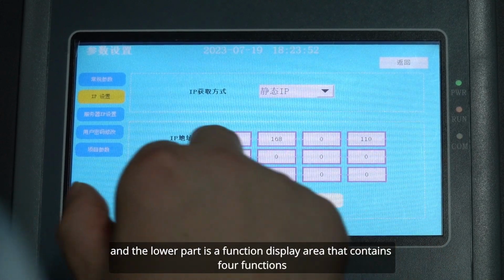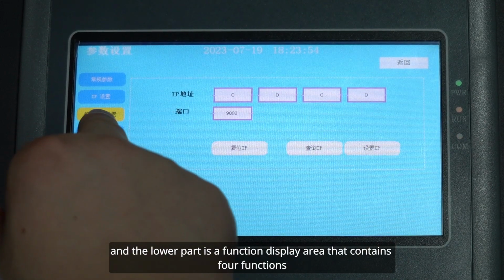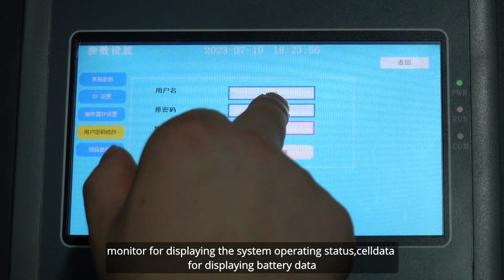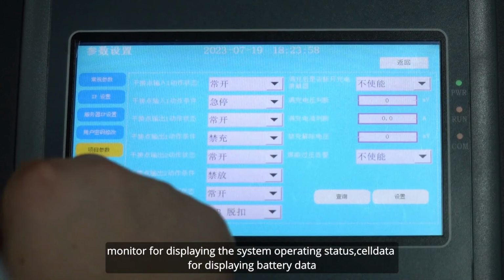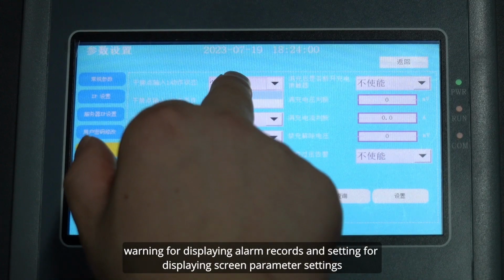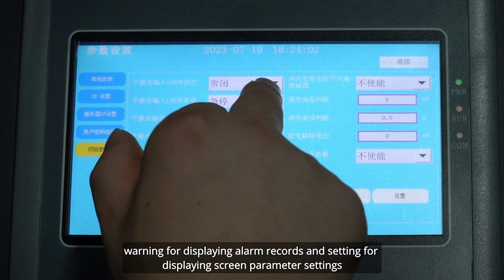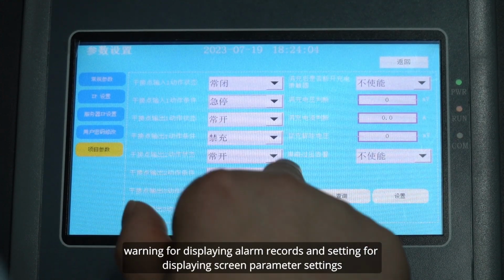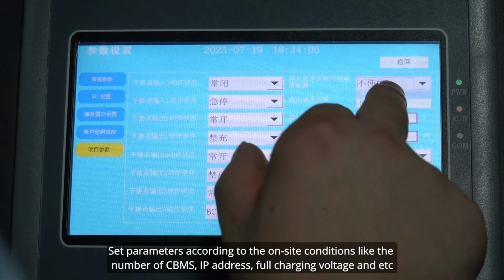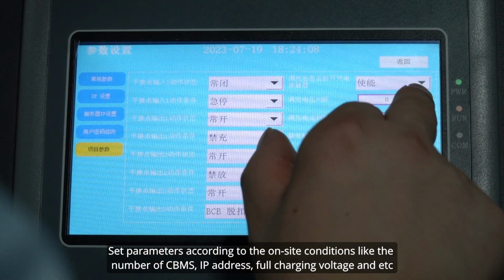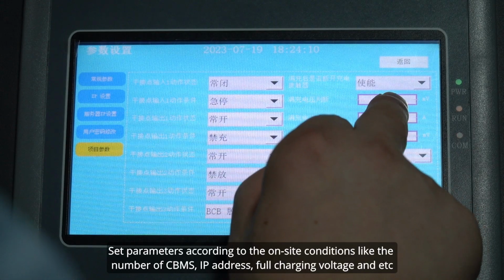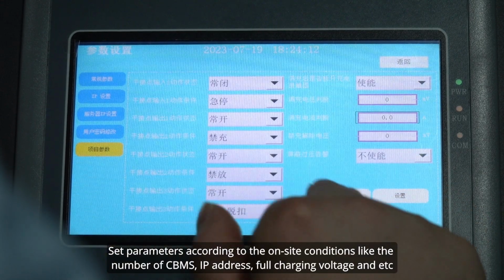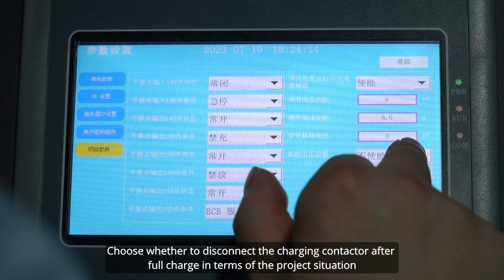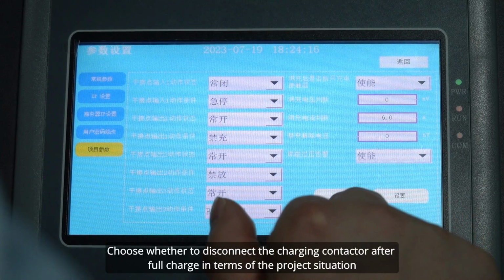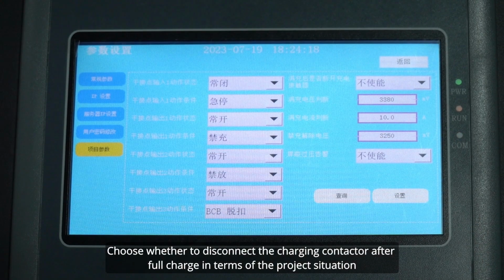is a function display area that contains 4 functions. Monitor for displaying the system operating status, cell data for displaying battery data, warning for displaying alarm records, and setting for displaying screen parameter settings. Set parameters according to the on-site conditions like the number of CBMS, IP address, full charging voltage, and etc. Choose whether to disconnect the charging contactor after full charge in terms of the project situation.